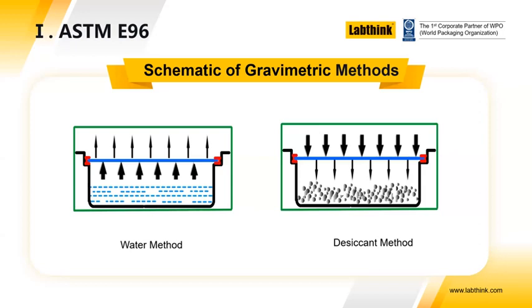In the desiccant method, the reverse is true. So we have high humidity on the outside going into the low humidity atmosphere inside the cup where the water vapor is absorbed by the desiccant. And in doing so, the weight of the assembly increases as the desiccant absorbs the water vapor. So in the method, we are measuring a weight gain. The whole assembly gains weight as more and more water vapor is absorbed by the desiccant.